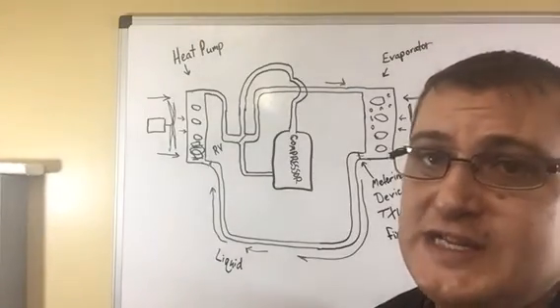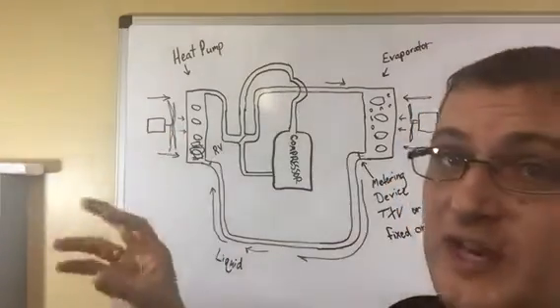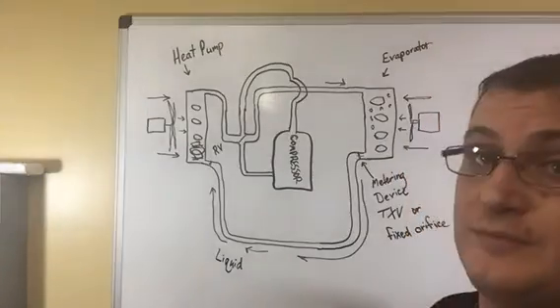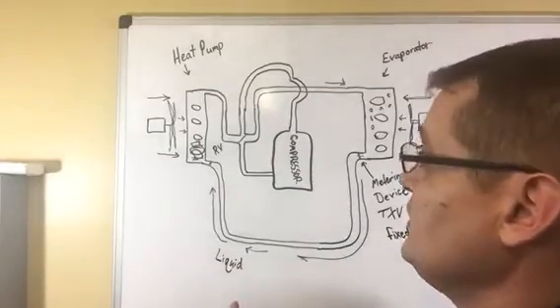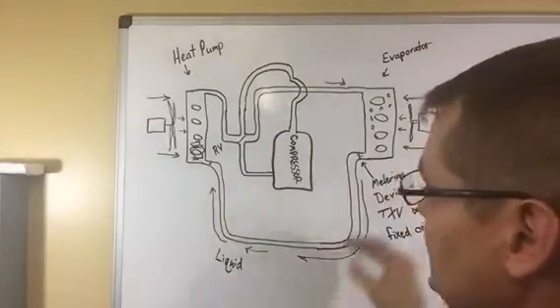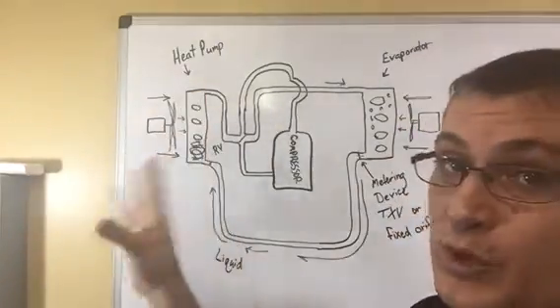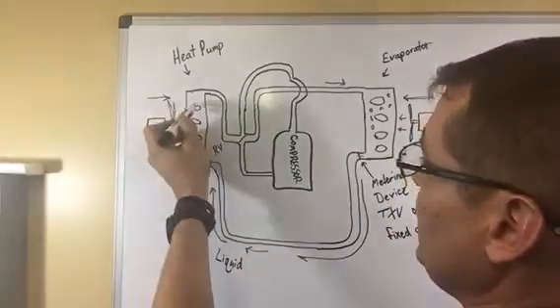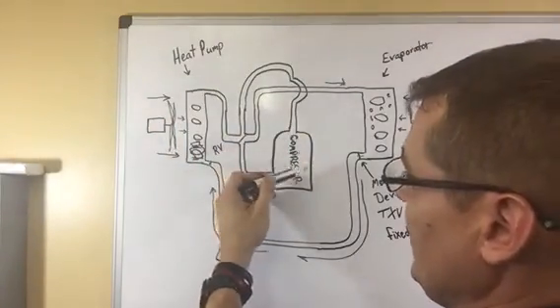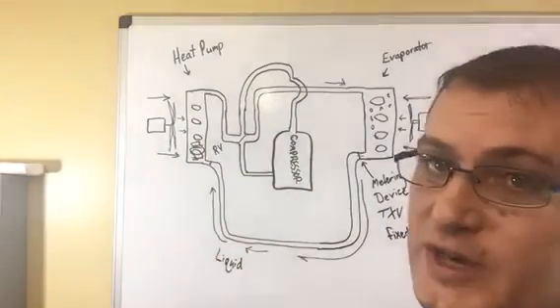Even if it's 40 degrees outside, it's still absorbing heat from outside air. So as it boils off and absorbs the heat, it is a vapor because it condensed back to liquid inside. Now it's condensed to a liquid and then sprayed off and boiled off into a vapor. So now vapor comes off and goes to the compressor where the compressor compresses that to a hot gas. So you can see all it does is switch the flow of refrigerant.